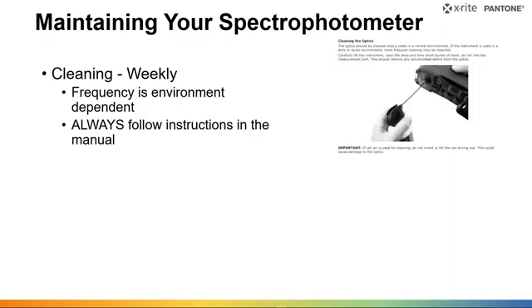For example, for a handheld CI6X device, that's a screenshot from our manual that shows the proper way to do it. We have the same thing for benchtops. So we tell you how to properly clean it. Mostly it's to keep dust and things out of the optics and out of impacting your measurement. It's also important that every time you clean it, you then recalibrate, because of course, if you calibrate and then clean, you've just changed it after you calibrated, and now you need to calibrate to realign things.